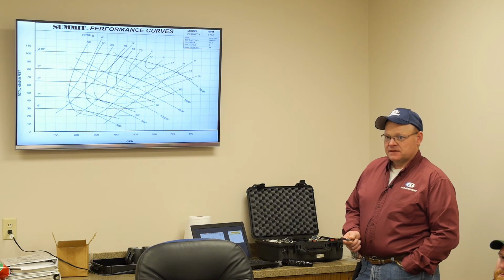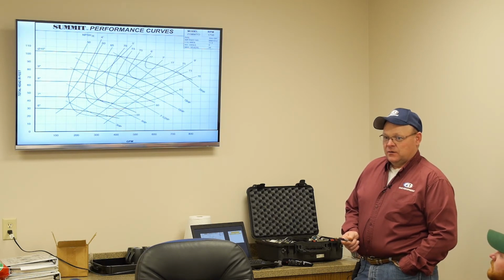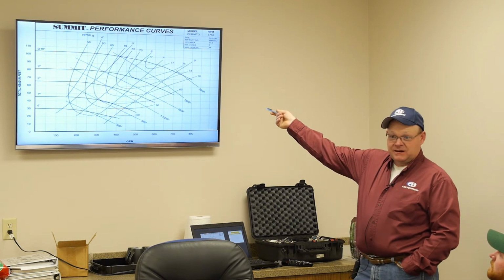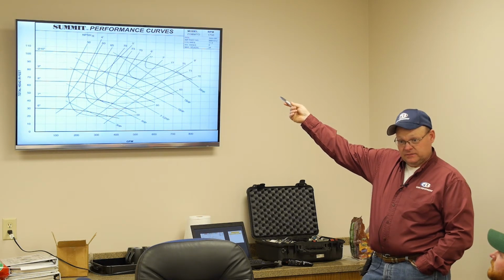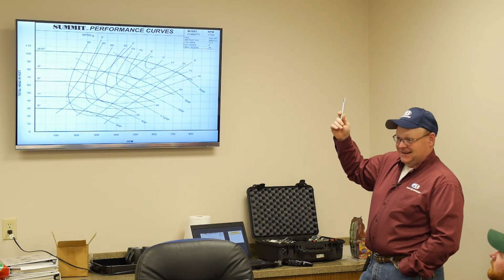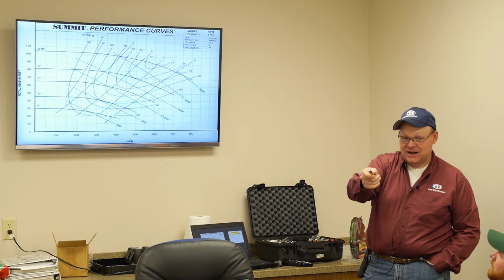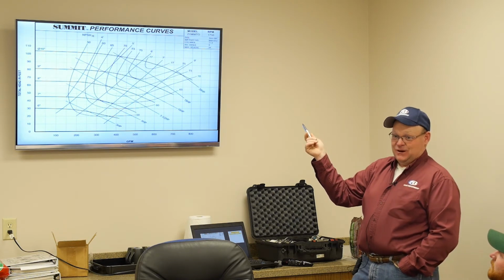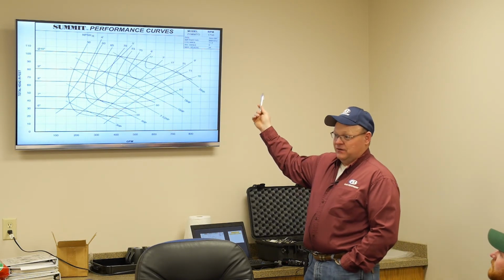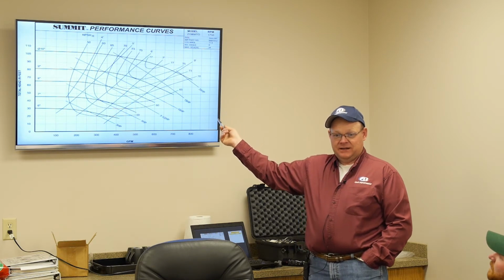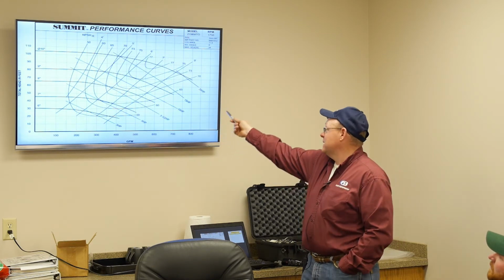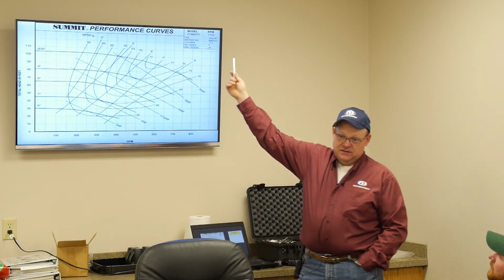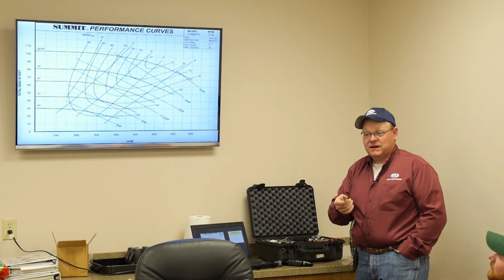The flow wouldn't keep up to feed the pump? Well, now guess what happens to your NPSH? You're right. You're exactly right. You're on the right track. Your NPSH went off the chart. So now you're 3 times what your NPSH requirements are. You're nearly at 27 feet out here. So you're exactly right. But a lot of people don't think about that.